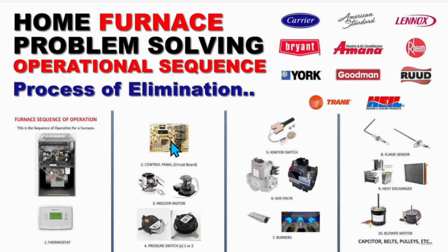If that works, then we go to the inducer motor. That's what you hear when your furnace first kicks on. Starts to create the draft. And there will be a click. Then there'll be another click on the pressure switch or switches. And you'll hear that when they close. Then you'll hear the igniter ignite and you'll see that glow in your furnace. If you don't hear those clicks, or if you don't hear that furnace come on, then I would start looking at the inducer motor. Sometimes things happen and these pressure switches get stuck either open or closed, in which case you're going to have to replace it.